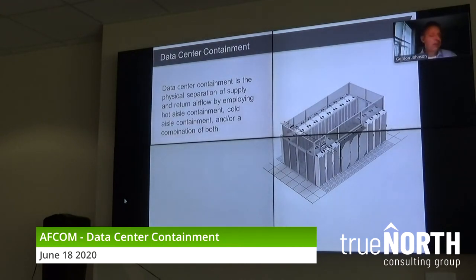Now, every now and then, we get a customer that, even after containment, says, I don't want to raise temperatures. I don't want to lower fan speeds. I like things ice cold just the way they are. And we can't change that. But for 99% or more people, after putting in containment, you're going to be able to do what's called room-level airflow management, or again, I'll shorten that to cooling optimization. Now, we'll see why that's the case.